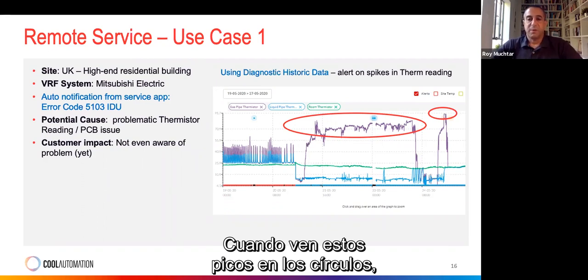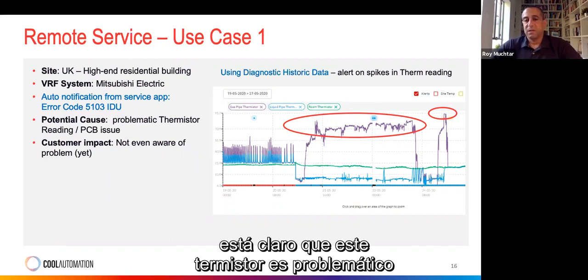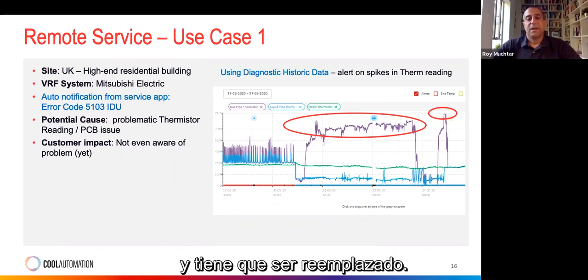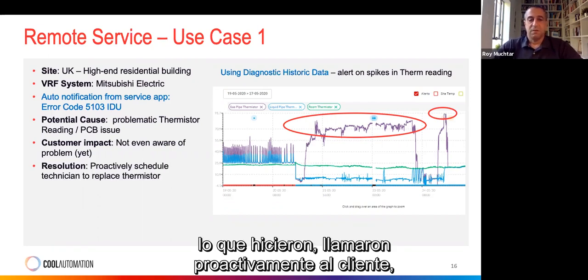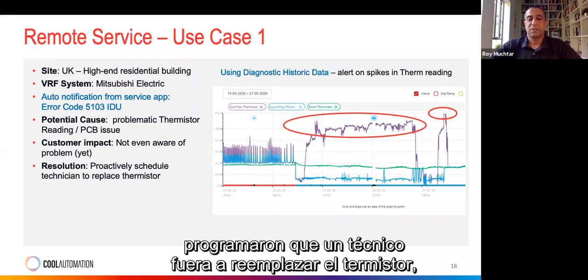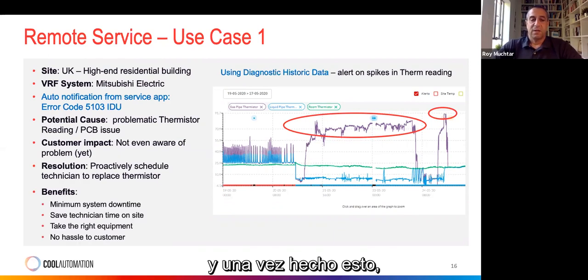When we see these spikes, circled here, it's clear that this thermistor is problematic and needs to be replaced. So what they did was proactively call the customer and schedule a technician to go and replace the thermistor, and once that was done, the issue was cleared.